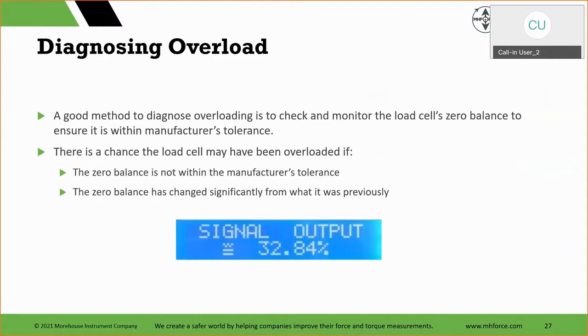That significant change. So if we have a zero balance that's 0.5%, 1% is the tolerance, and then it changes to 1.5%, and the output of the load cell changed too, that might be okay. But at least you will know that somewhere someone most likely put above 150%, and they basically shifted my curve, right? They shifted the output. You're still within that gray area of 1.5% to 5%. You may consider replacement, or you may say, look, I'm still good. It's still operating, it seems to check out. My temperature variation is not that large, and therefore I'm okay with it. We've seen that go either way.